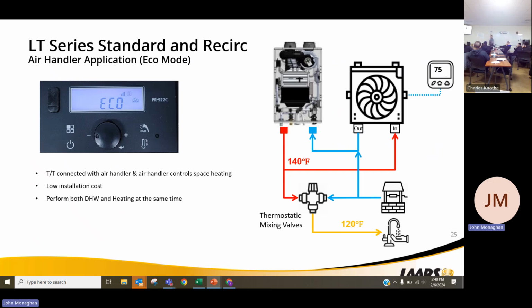Unless you put it into commercial mode, then you can go to 160, go up to 180. Residential, you can only go to 140. Actually, you have to change the fan limit to go on at 140. You just have to tell it you're using other than PVC. No, I mean the air handler. I thought the air handler's fan limit doesn't go on until 160. No, some of them will go down to 130, 140, depending on what model it is.